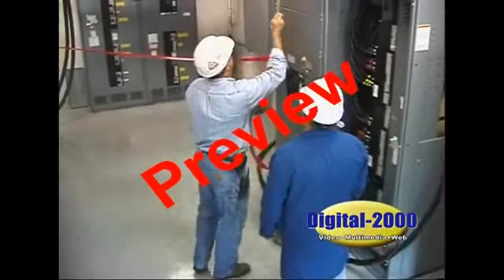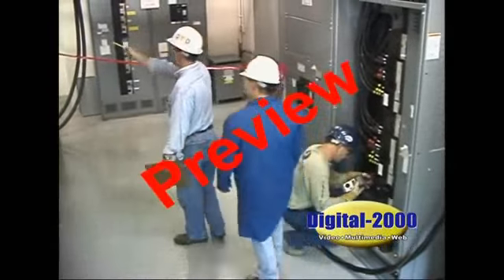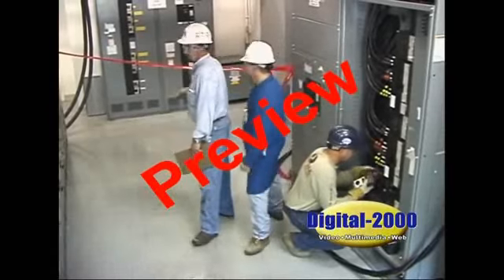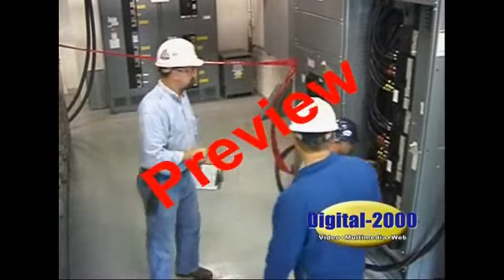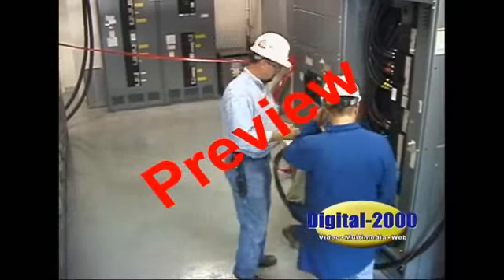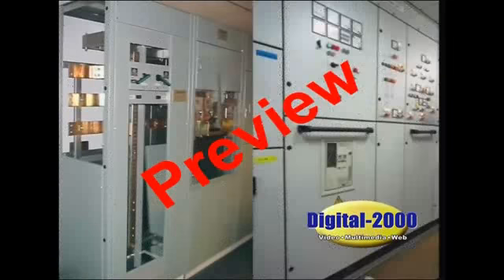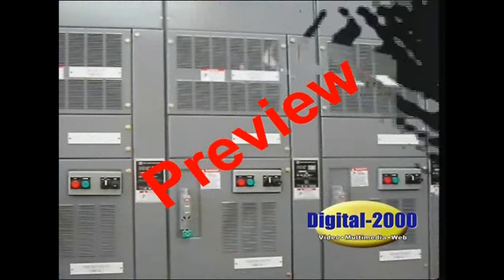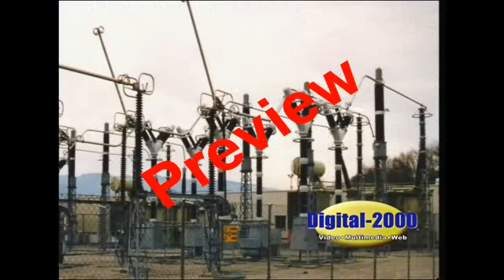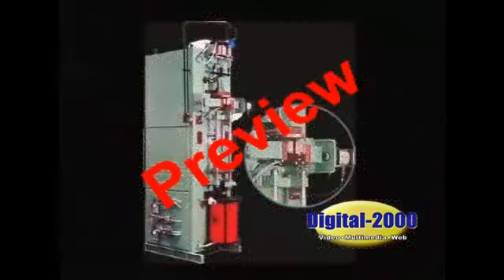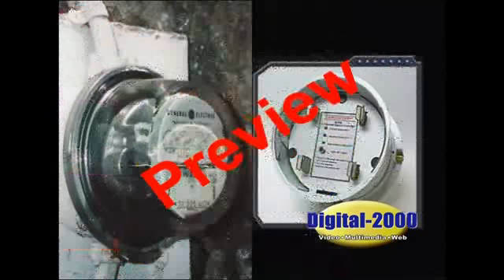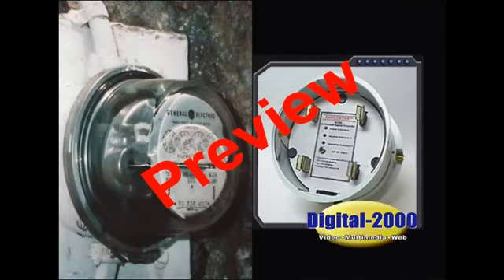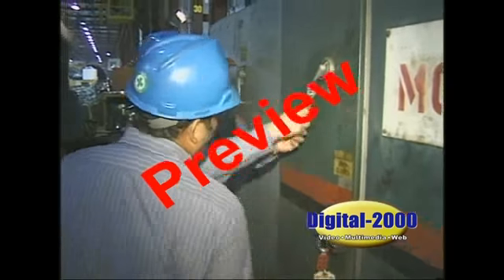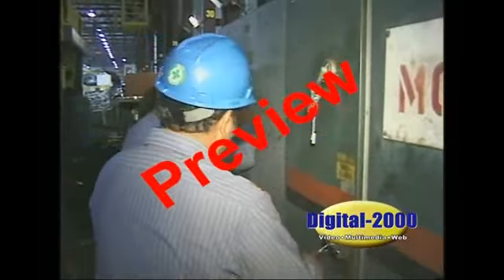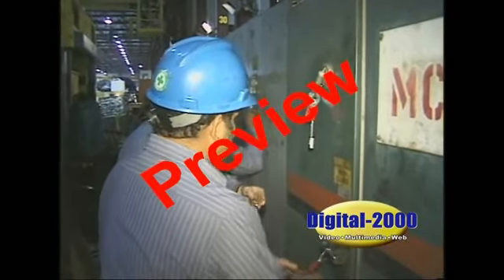Where and when to expect arc flash hazards. Hazardous arc flash can occur in any electrical device, regardless of voltage, in which energy is high enough to sustain an arc. In industrial settings, common places for a fault include panel boards and switchboards, motor control centers, metal-clad switchgear, transformers, motor starters, high voltage switching and grounding, pad mount switching, meter bases and meter banks. Any place that can have equipment failure. Some of the employees that are affected by arc flash hazards are maintenance workers, electricians, operators, and HVAC personnel.